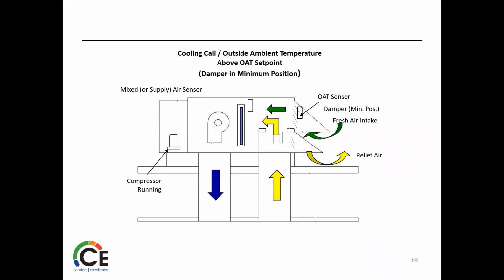So now the outside ambient temperature is above the OAT set point, right? So now dampers are at their minimum position. So we're still bringing in a little bit of outside air, but not much. We're still using the indoor air and the outdoor air, return air, throwing it through a coil with a compressor operating, just like normal cooling.